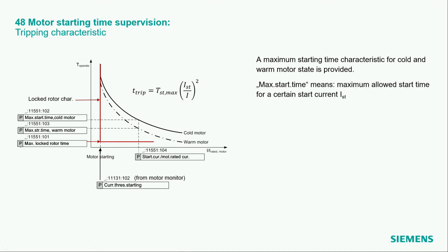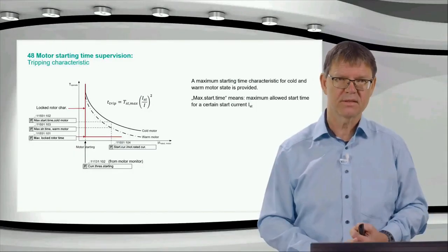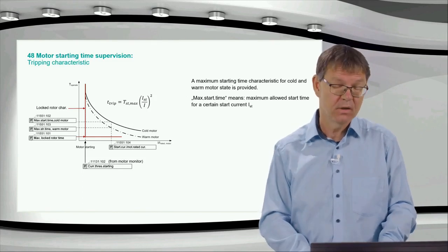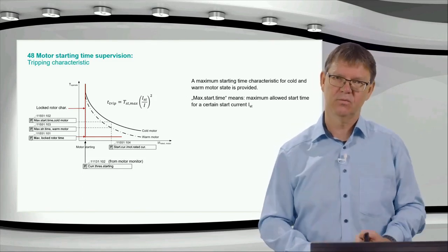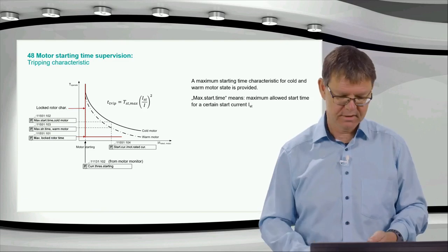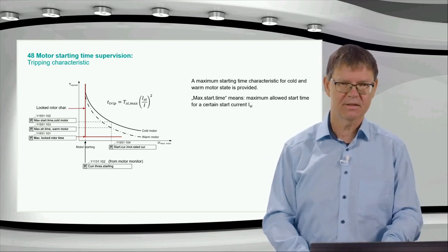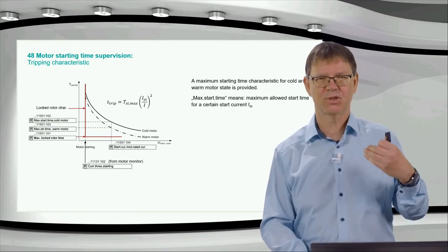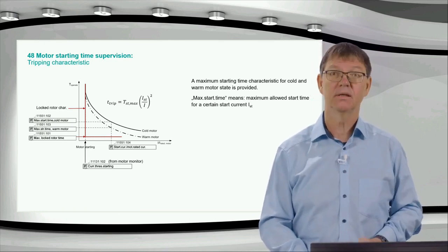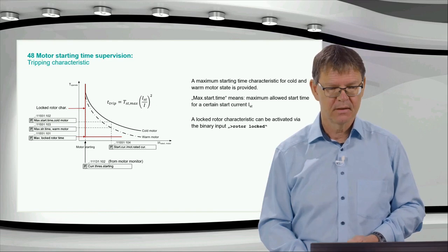Maximum starting time again means the maximum allowed starting time for a certain start current. We get this from the motor manufacturer as data. Either there is a curve, I'll give you an example later, or it's a value which we can enter here. It is not the standard starting time, because this normally is much below the maximum startup time.